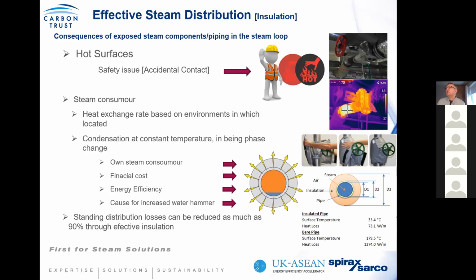The benefit these insulation jackets offer is that, should you need to do maintenance on the valve, you can remove the jacket through one of your own craft technicians without the need for specialist insulation companies, so we can ease the maintenance issues. In the case example here, for steam at about 10 bar, the surface temperature would be 180 degrees. Whereas if you use the insulation jacket, you significantly reduce the surface temperature, and you can see quite a dramatic reduction in the energy loss.